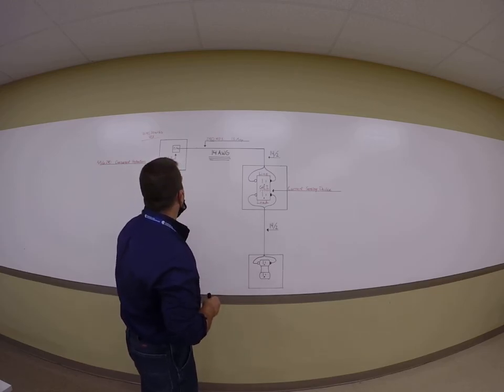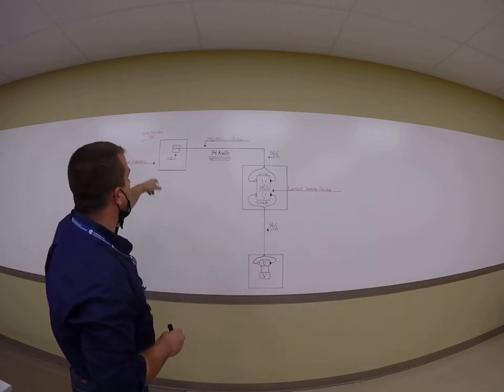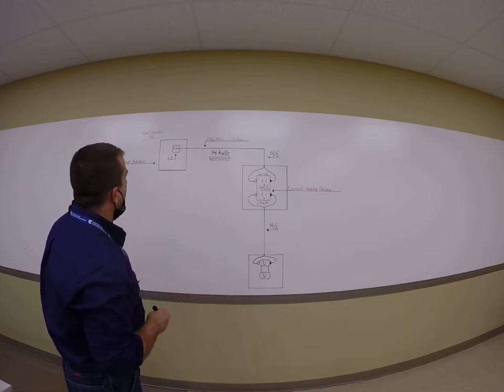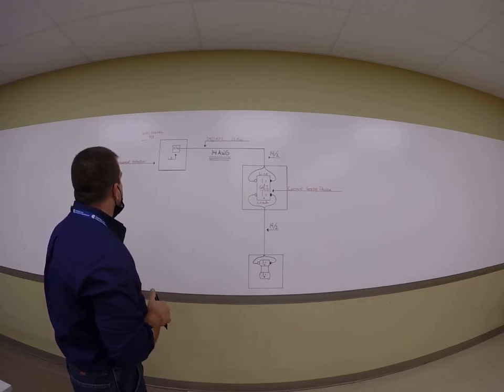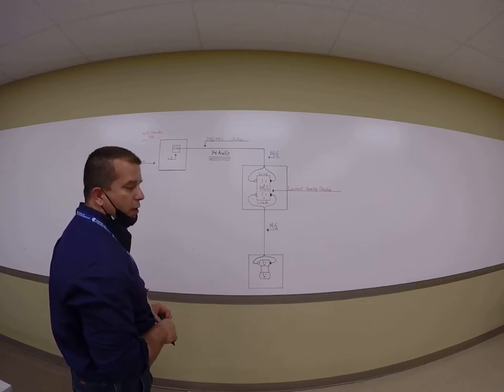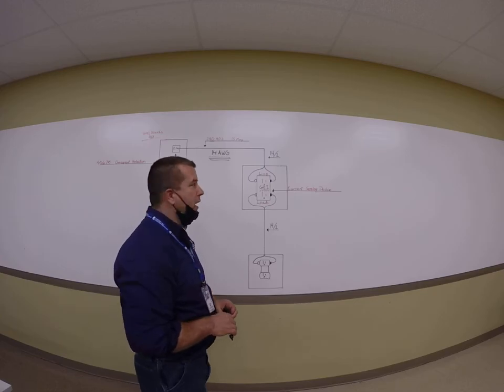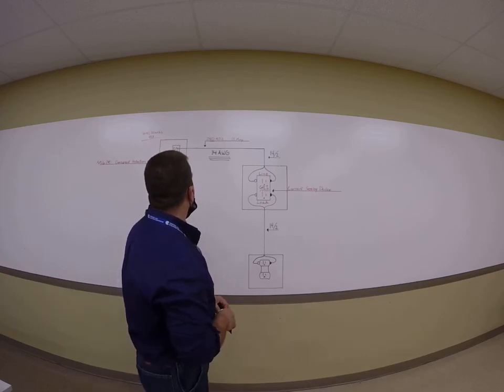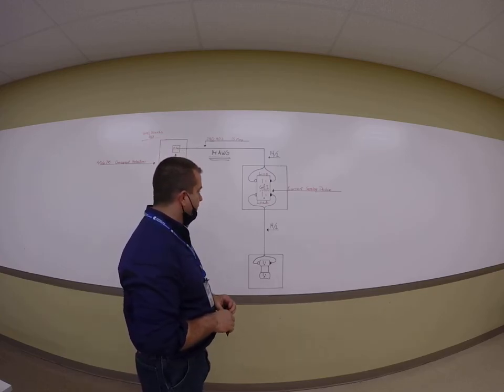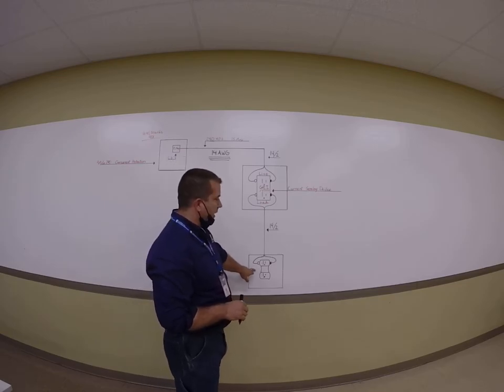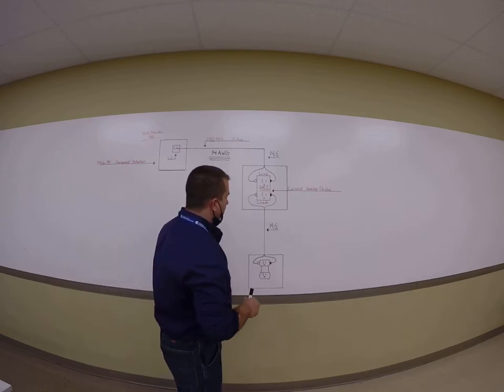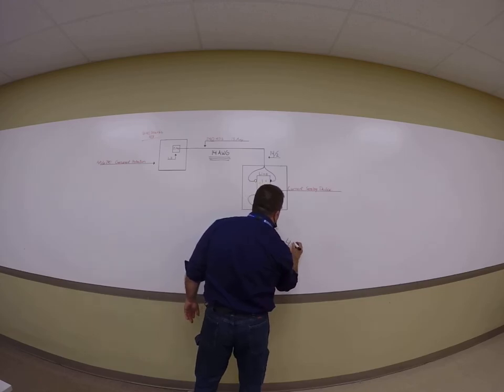I wanted to throw that in there again, as well as any other articles that are on this wall, to reiterate where to look. So circuit breakers are found in overcurrent protection, 240. Your standard circuit breaker sizes are 240.6(A). And then panel boards are found in Article 408. And receptacles, and I'm going to get to this in a second, receptacles is Article 406.